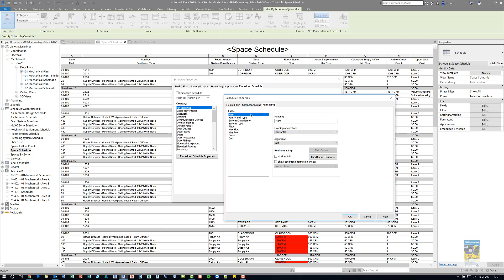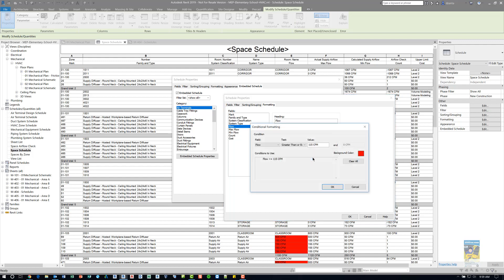The formatting tab gets into how the data looks within the cells. For example, for flow, we can specify conditional formatting as well as total calculations. I have it set up so that if the flow is greater than or equal to some number that I've specified, it will color that cell red so we can visually see which particular air terminals meet this criteria.